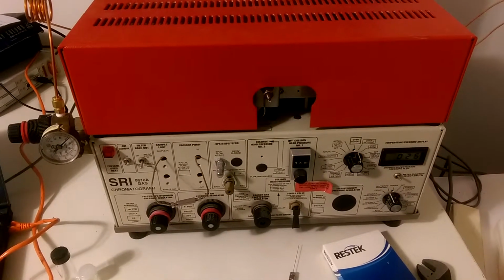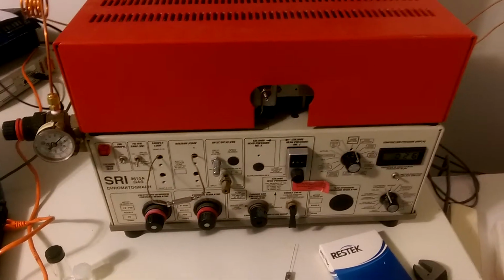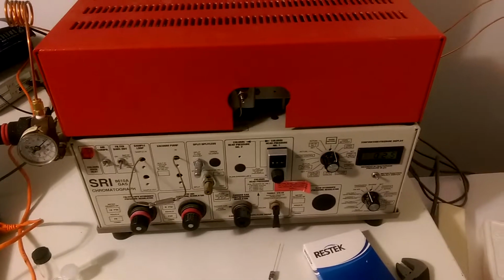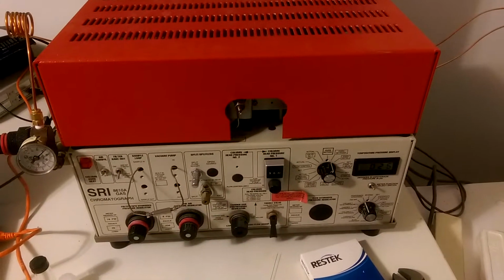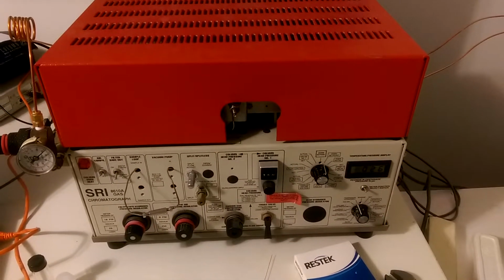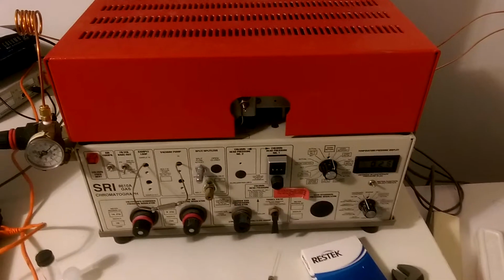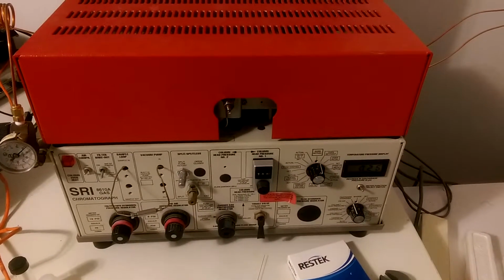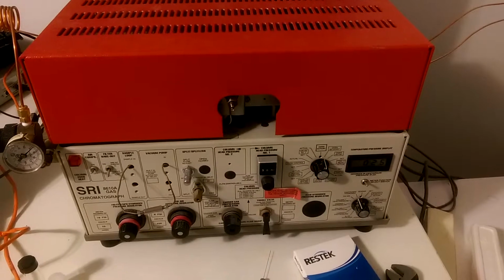Okay, here's an SRI 8610A GC system. The unit is fully operational, includes an FID and TCD detector, which are in series. Depending on how you plumb the system, you can either use the FID alone or the TCD, or you can use both of them in series.